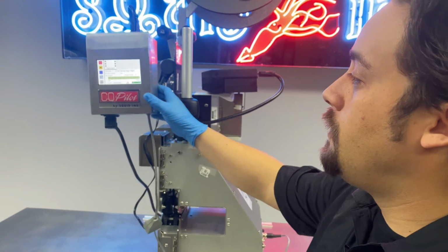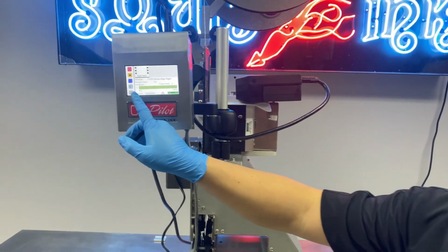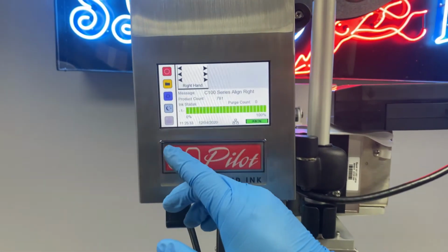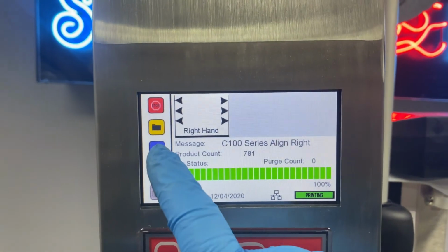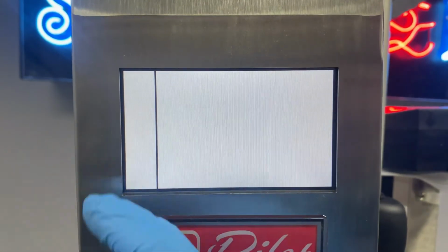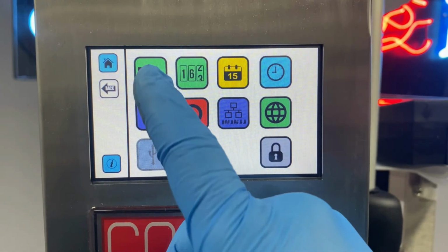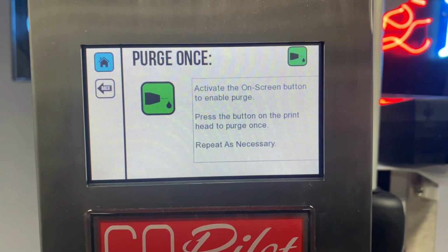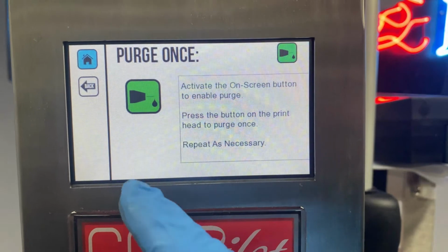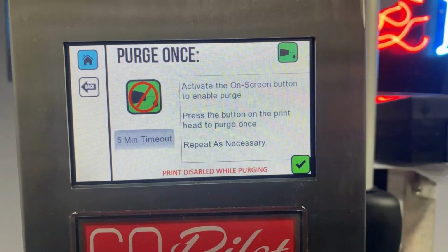Before we go any further, we need to go to the controller and tell it we're going to purge the head, which we do by accessing the parameters page and selecting the Purge icon in the upper left-hand corner. Once you're here, press it one more time to confirm.